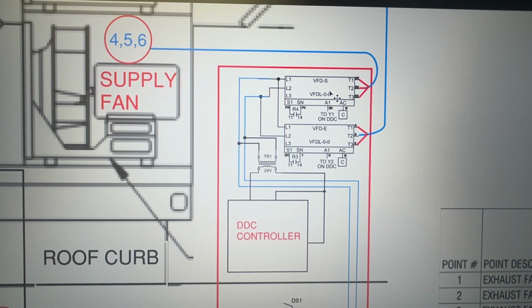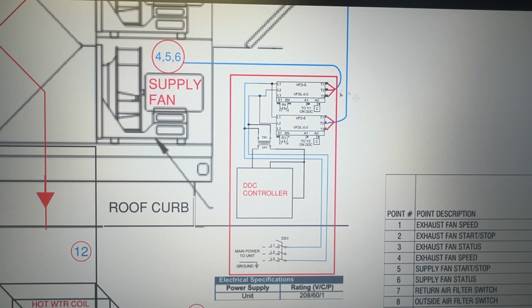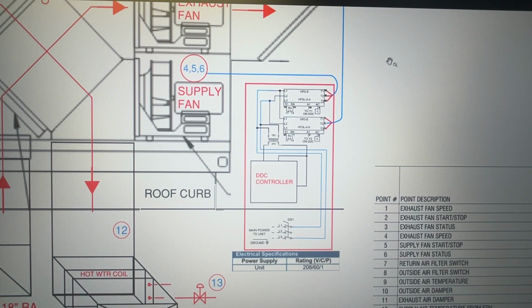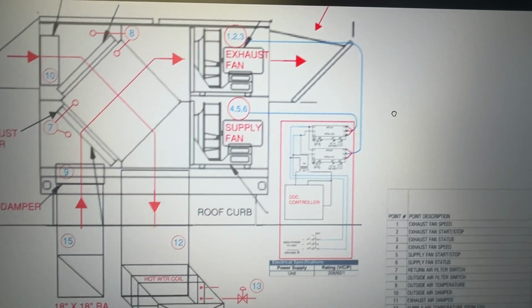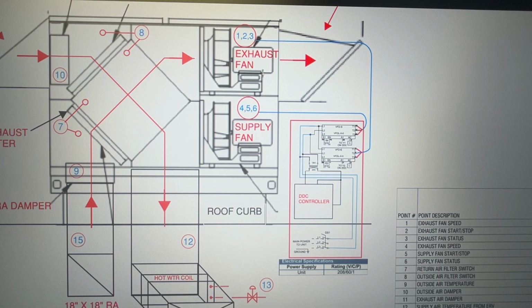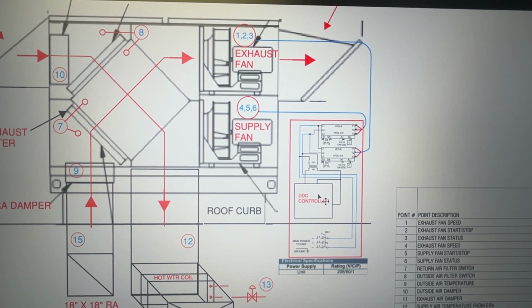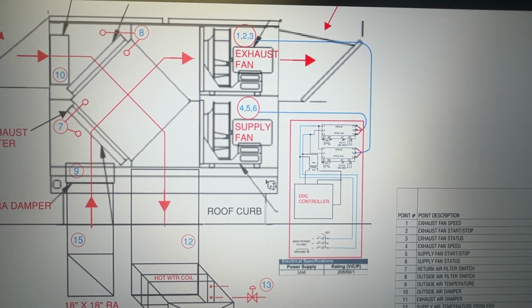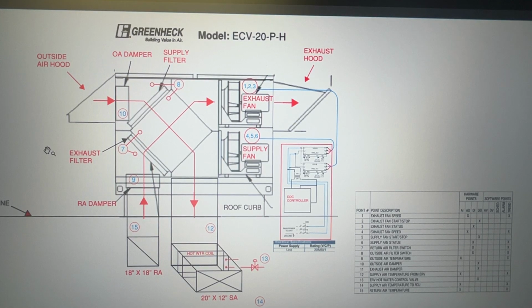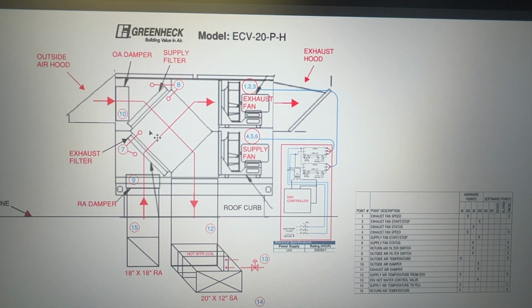So that VFD is adjusting that fan speed as required. So that wiring there goes over to the supply fan, and same for the exhaust. So all these points that I have shown here, they all get back to the controller. The controller then takes that information and, based on set points, adjusts accordingly. So for number 10, we've got an outside air damper. That point will go back to the controller. So that will open and close to allow fresh outside air in.